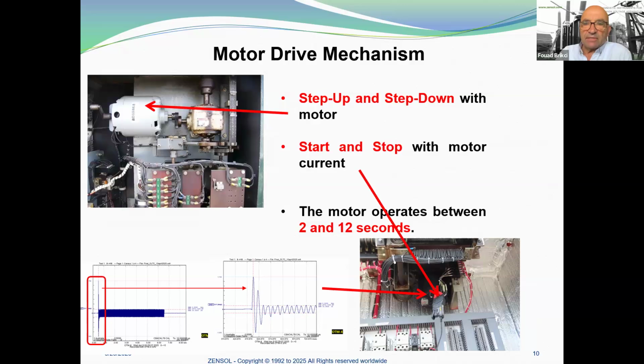So the motor drive mechanism: this motor allows the tap changer to move from one position to another. In recording and analyzing the AC or DC current of this motor during the step up or step down operation, we are able to know if the mechanism is forcing or not. The motor current also allows us to start and stop the recording. And usually the motor operates between 2 and 12 seconds.